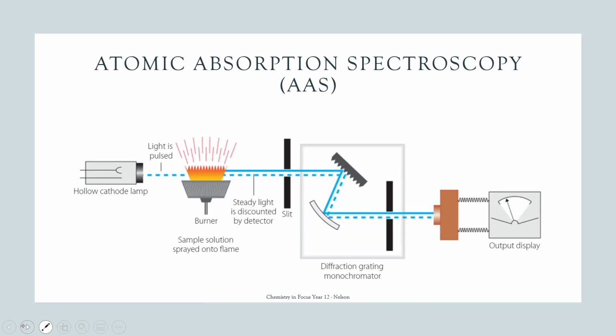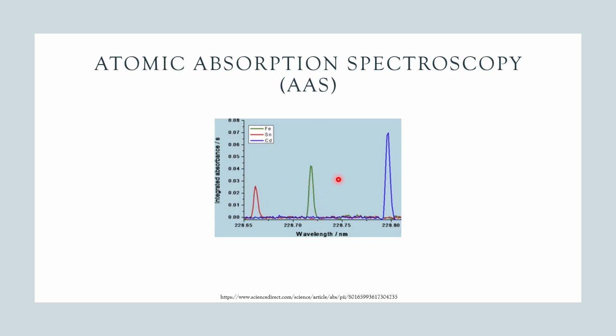It works really similar to UV Vis, but instead of figuring out how much light is being absorbed by the sample in a solution, we instead vaporize the substance, forming ions as gas. We then put light through the sample, seeing how much is actually being absorbed. It goes through a monochromator so that we can measure each wavelength at a time and figure out how much of the light is actually being absorbed. In a similar way, we can get different metals or different substances. So here we have a bunch of different kinds of metals showing different absorptions at different wavelengths.